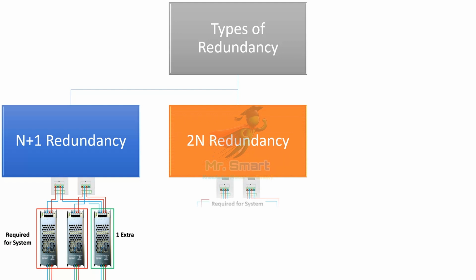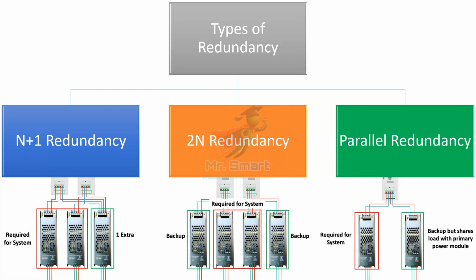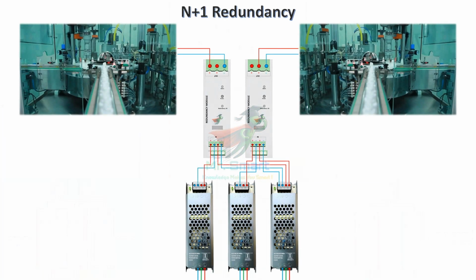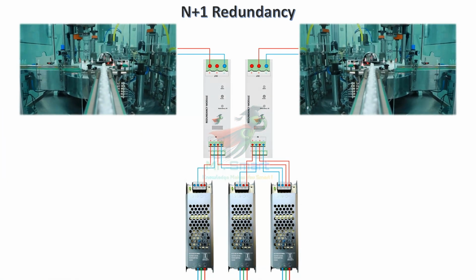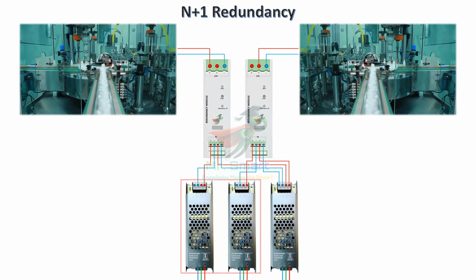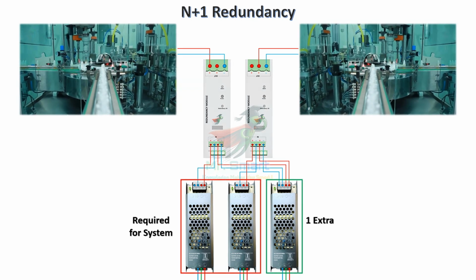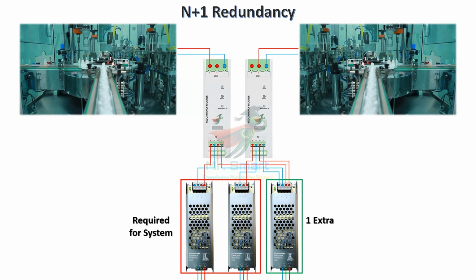Redundant power supplies come in a few different types, and some of the widely used redundancy system types are N+1 redundancy, 2N redundancy, and parallel redundancy. In N+1 redundancy, you have one extra power module beyond what's needed. For example, if your system needs two modules, you have three in total.